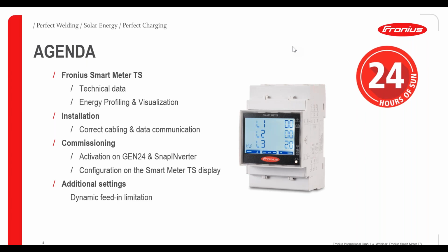Energy profiling means that we are using more than one smart meter in a system, in the installation. So if we have a secondary smart meter or even more smart meters in the system, for example the primary smart meter in the feeding point of the PV system, and then an additional smart meter for specific loads whose specific consumption we want to know, then we add an additional smart meter in the consumption path of those loads. For example, if you have a heat pump, an air conditioning, or an electric vehicle, then you can know the exact consumption of those specific loads.